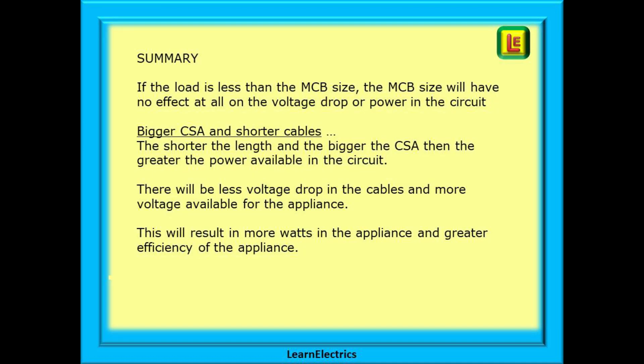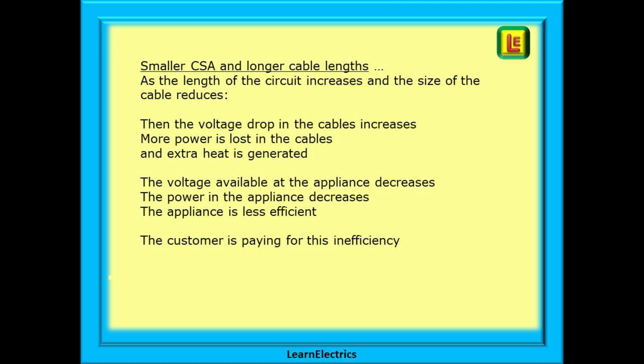A short summary of key considerations: if the load is less than the MCB rating, the MCB size has no effect on voltage drop or power in the circuit — we included it deliberately to show this. The shorter the cable length and the bigger the CSA, the greater the power available, with less voltage drop in cables and more voltage for the appliance — resulting in more watts and greater efficiency. As circuit length increases and cable size reduces, voltage drop increases, more power is lost as heat in the cables, and both voltage and power at the appliance decrease.